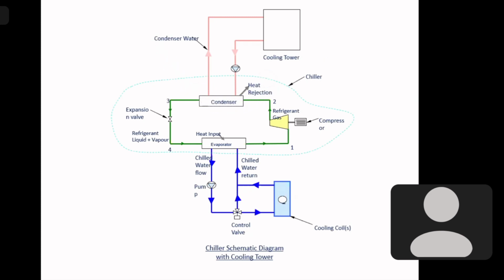In this shell and tube heat exchanger, the refrigerant is in the shell and water flows through the tubes inside. Water cools the refrigerant, and it comes out from the condenser as a little warm liquid refrigerant. But in the process, water gets heated up. So we don't throw out that hot water. We take that hot water back to a cooling tower. A cooling tower is equipment where the water is sprayed from the top, and there is a fan which sucks air.